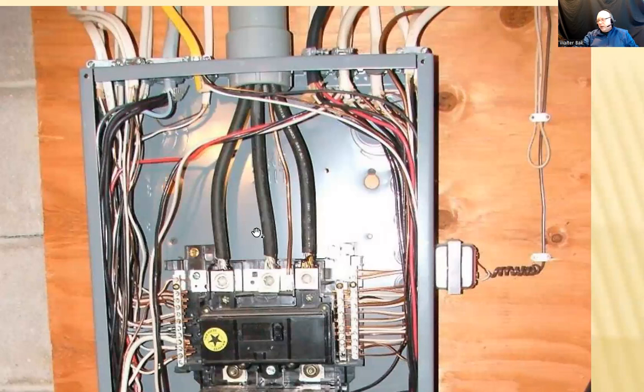If the grounding wire goes from this panel into the receptacle, that receptacle is pretty much electrically grounded, but because there is no straight, uninterrupted, solid or stranded wire that goes directly to the true ground, we call that receptacle bonded. You say that it's bonded instead of grounded. It's still electrically grounded, at the same potential as ground, but physically there is no one uninterrupted wire going from that device to true ground. It goes through the electrical panel and then to the true ground. Then we're calling that bonded, right? Same thing, ground or bond, electrically the same thing.